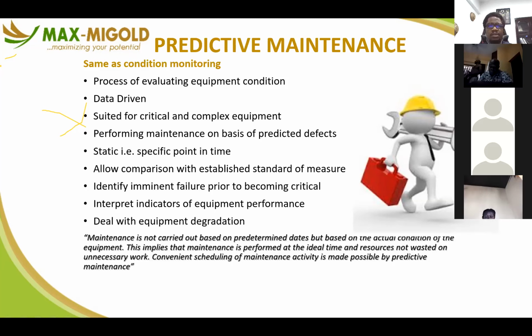Every asset you have, especially heating, cooling, and moving parts assets, has parameters set by the manufacturer. Take your generator, for example: there's a temperature range for normal operation, an oil range for normal operation, a vibration range, a pressure range, a sound range, and so on. As you're monitoring and gathering data, you want to ensure your operating parameters are staying within the range of each parameter.